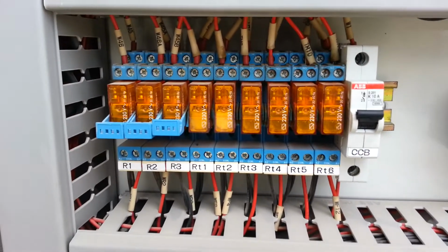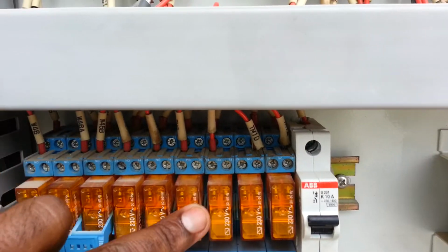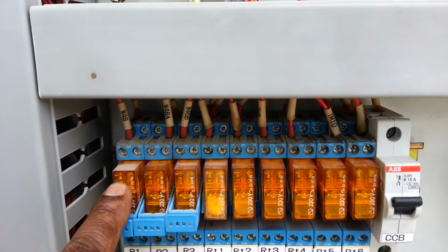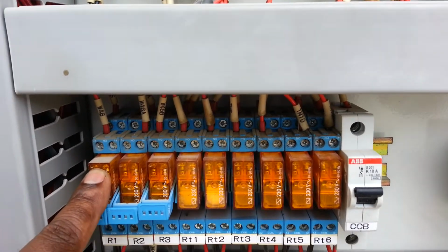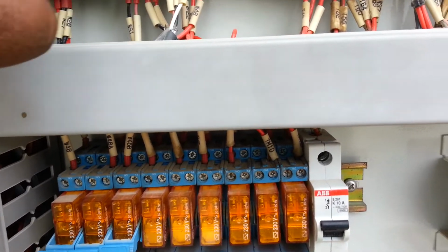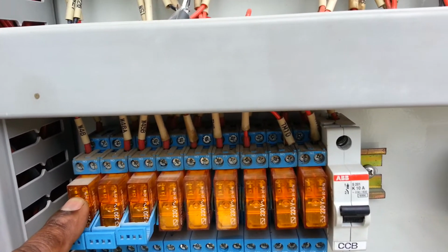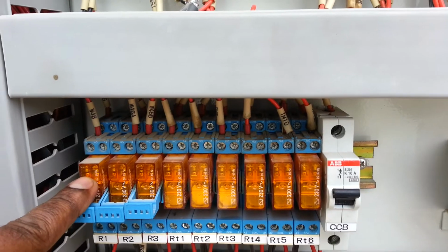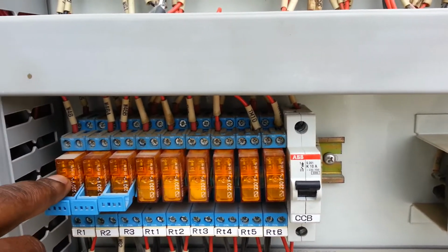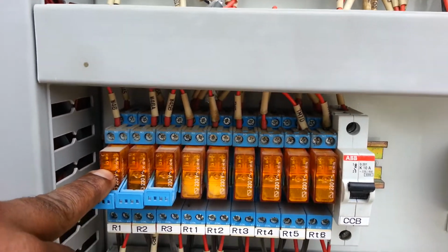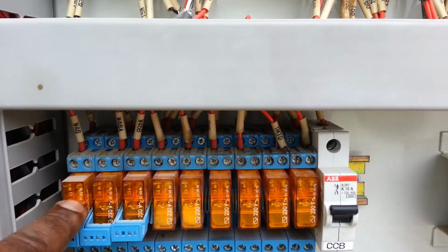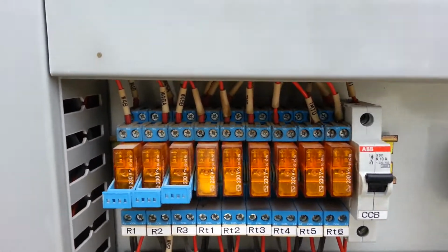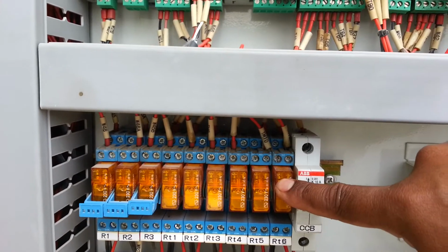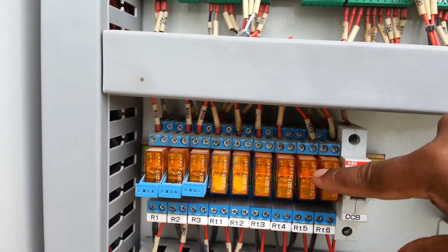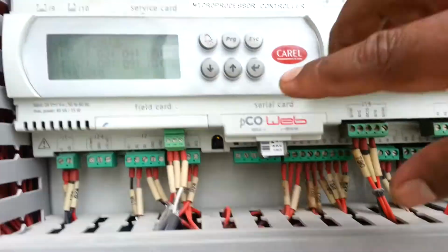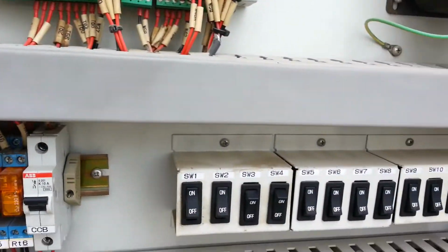And here, you can see, is a small relay. Actually, this is also a supporting relay. The primary command comes to this relay, then this relay gives the command to this. This is an analog relay. And all of these are for compressor status and the fan. Any problem in the fan motor or in the flow switch all comes primarily to this relay, and this relay tells this what the problem is, and it shows in this display.